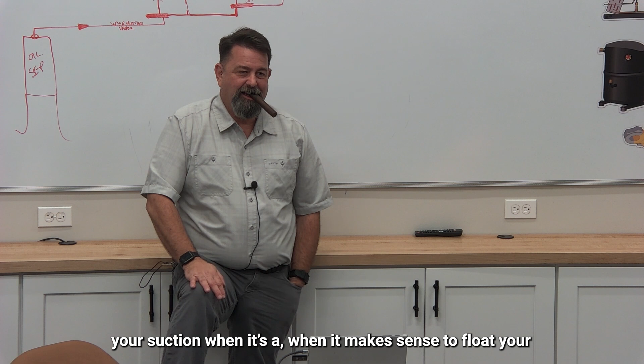So his question is, because I'm changing the set point of my suction group on the rack, is that going to cause my compressors to actually cycle? No. Well, it can, but in theory, no, it shouldn't, because you're only floating your suction when it makes sense to, in low load situations and stuff. So it's going to be a small number of PSI, not huge. Let's say I've got a 6-degree rack, or 10 PSI rack, I guess would be more.